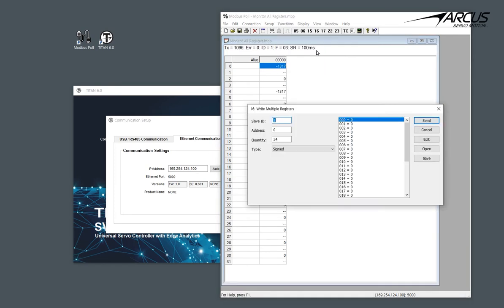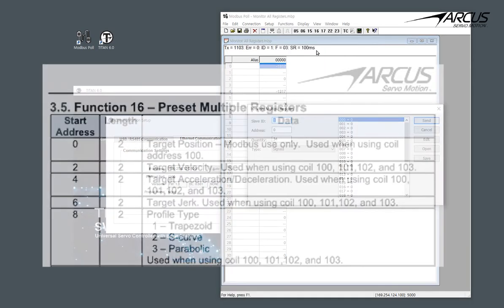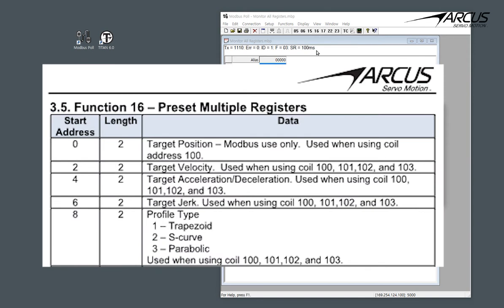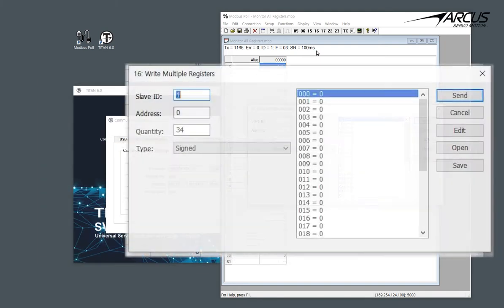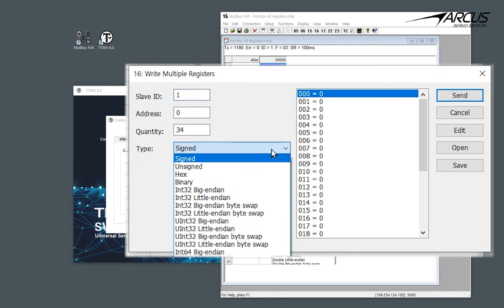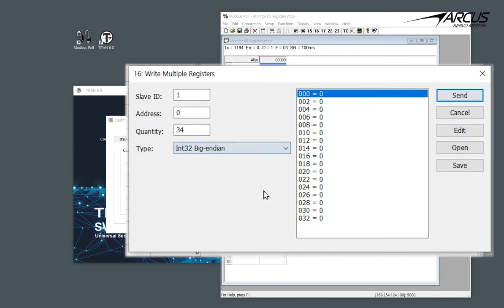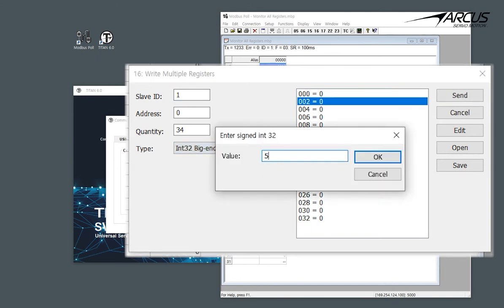We know that the speed starts from address 2, acceleration from address 4, jerk from address 6, and profile type from address 8. We will set the format to 32-bit signed Big Endian.